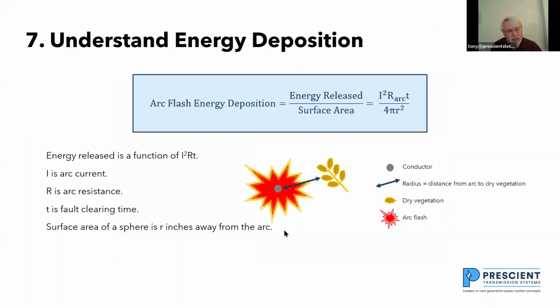So if you're talking about energy deposition, there are two ways we can release energy from a transmission line or distribution line. The first is arc flash. That's what we wear the arc flash resistant clothing for, when we're doing switching in a substation someplace. The energy deposition is just a function of energy released divided by surface area. The energy released is I squared times the resistance of the arc times time. Well, it turns out the resistance of the arc is pretty easy to calculate.